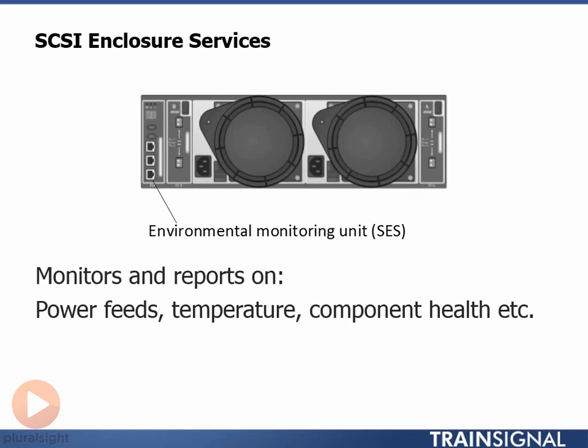As well as monitoring all of these, the SCSI environmental subsystem can tune things as well. A common and simple example is ramping up the blower speed if the temperature in the drive enclosure rises, and then slowing down the blowers when the temperature returns to normal. In all of this monitoring and management, the environmental monitoring unit reports back to the controllers. And some environmental subsystems can even sound audible alarms to alert staff walking the data centre floor of failure conditions.